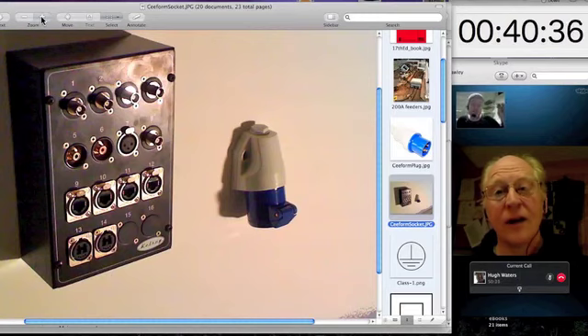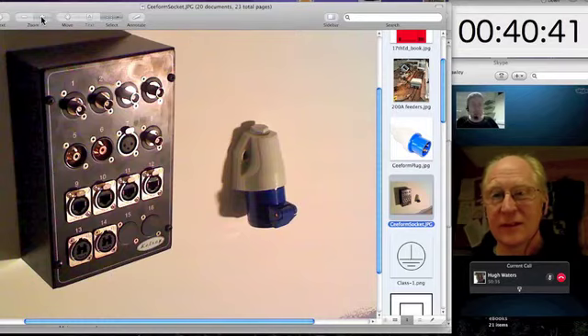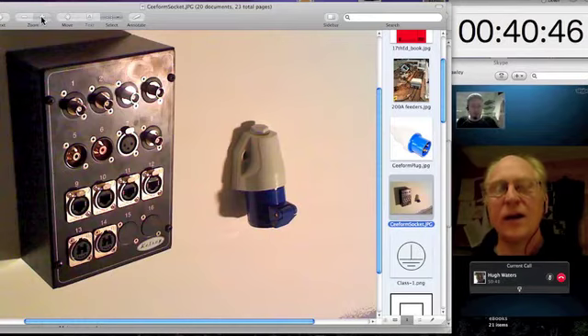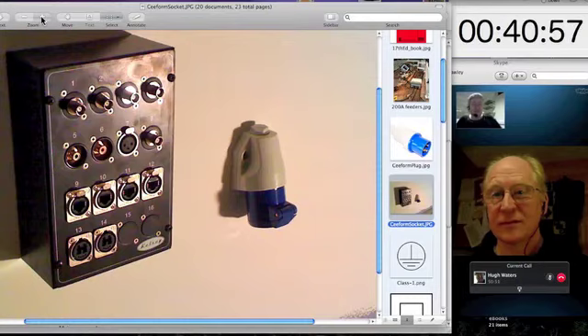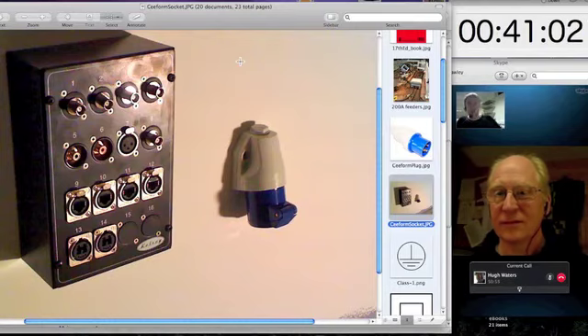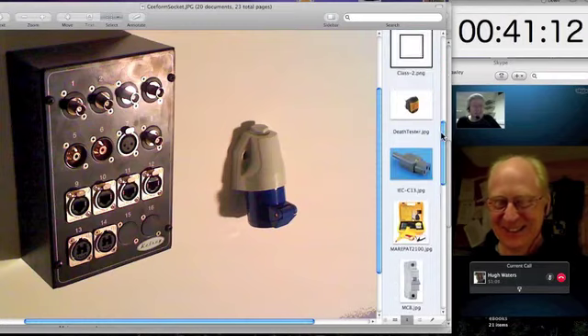And so the screen on the video cable, which of course was carrying technical earth back from the machine room, was now tied down to the building's earth, because that plate is mounted on the wall. The walls were stud partition walls, so there's a steel frame within the wall. And just by virtue of the fact that the whole building sits at kind of earth potential, that was the case. As soon as I went back to the machine room, unplugged that video feed, leaving the machine room, going to the big plasma screen in reception, the hum all disappeared everywhere. And I was kind of hailed the returning hero, but it had taken 2 days to find where the problem was.